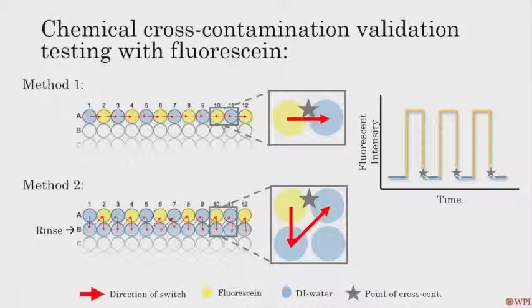And so after we got everything moving the way we wanted it to, we conducted a cross-contamination validation test. So we did this using water and fluorescein, and we just tested 2 different methods. Our design constraint was that the maximum cross-contamination could only be 0.01%, and so we wanted to keep the level of fluorescein in water wells less than this amount.